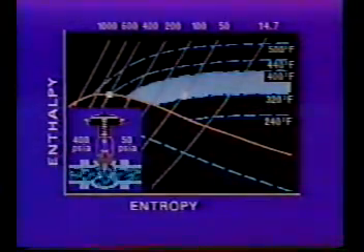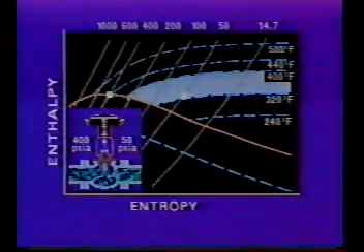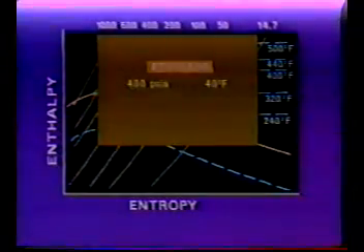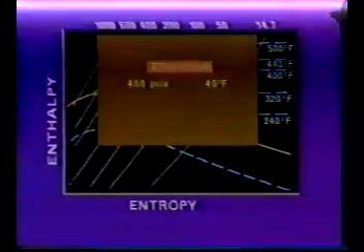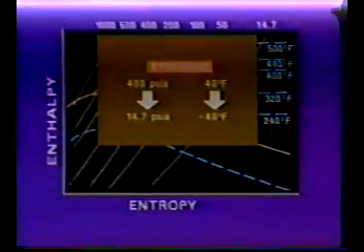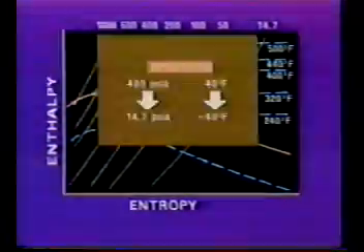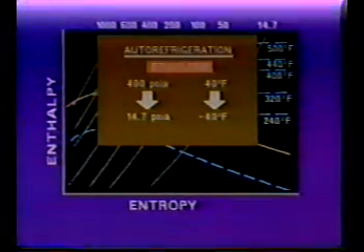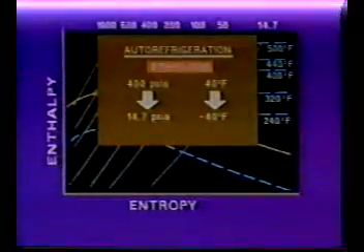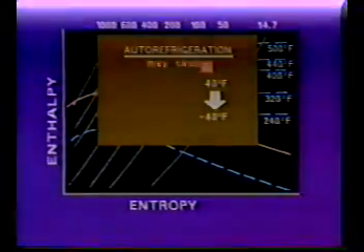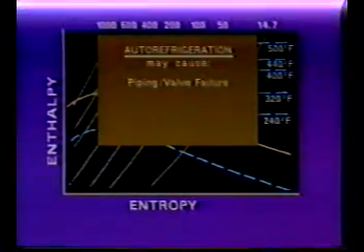Most fluids undergo a temperature drop when throttled, although many result in much lower temperatures. For example, when ethylene at 400 psia and 40 degrees Fahrenheit is reduced to atmospheric pressure, its temperature will fall to about minus 40. This effect is called auto-refrigeration, and many fluids are subject to it. If low temperatures like this occur unexpectedly, problems can develop. Valve and piping materials may not tolerate them, and failure may occur.